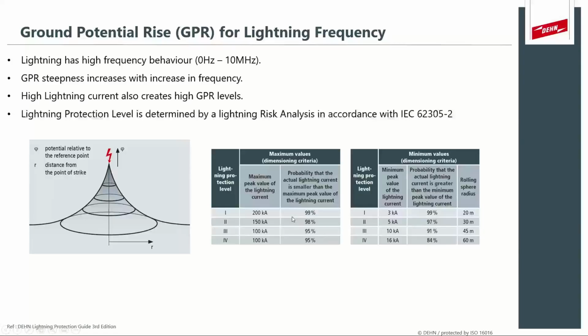Okay, and we do get asked this quite a lot. So lightning has lightning protection levels to which we design for our electrical system and for the lightning protection system. And it changes from lightning level 4, being the least amount of protection required, up to level 1. And this level is determined by means of a lightning risk analysis in accordance with IEC 62305-2. And this takes a lot of factors into consideration, like the lightning activity in your area, the dimensions of your building, fire risk, and so on. But it's worth knowing what lightning level you should design to.